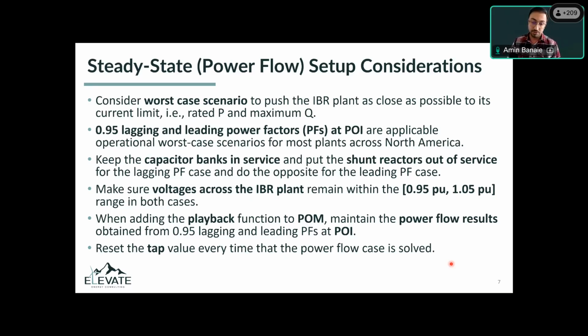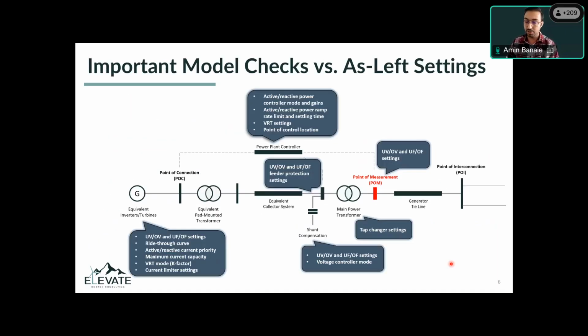Another factor when setting up your load flow case in PSSE and PSLF, specifically, is that this 0.95 lagging and leading applies to POI, but PRC-029 applies to POM. So if I go back here, this is POI where we're going to have 0.95 lagging and leading power factors, and this is where POM is and where PRC-029 is applicable. So when setting up your power flow case, you solve it for 0.95 at this point. And then when you want to connect your generator or playback function to this POM, you're going to remove this tie line. And if you solve your power flow again, then the P, Q, and V that you calculated here is going to change.